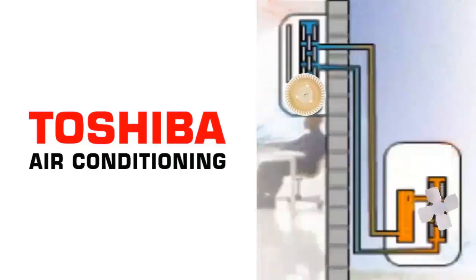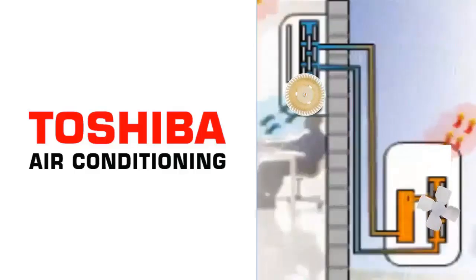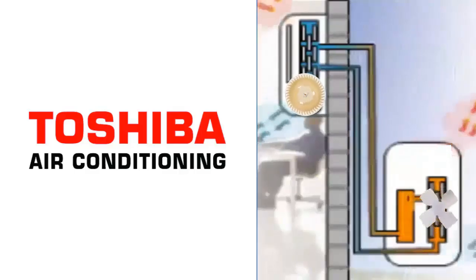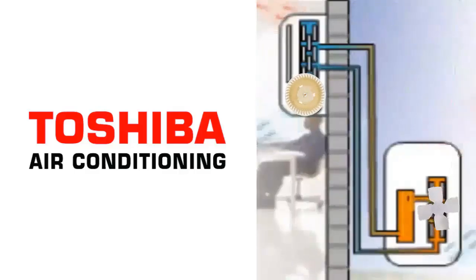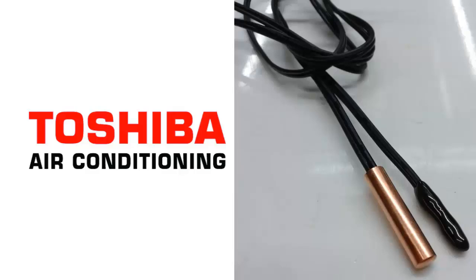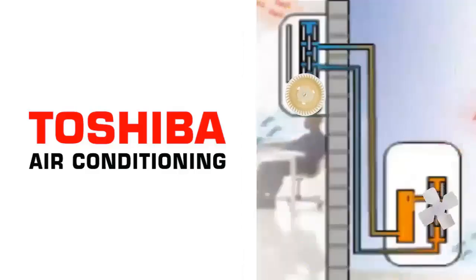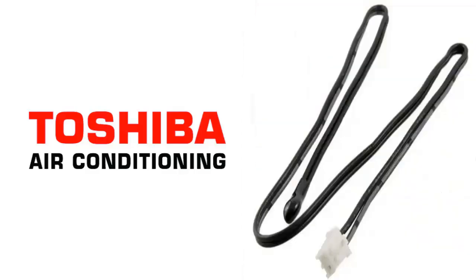In this video, we will analyze the list of error codes in Toshiba air conditioners, focusing specifically on those issues related to temperature sensors. Let's start by mentioning that most error codes due to temperature sensors are caused by presumed open circuits or short circuits in the sensor. We will classify these errors according to the sensor's position to facilitate understanding and potential solutions.